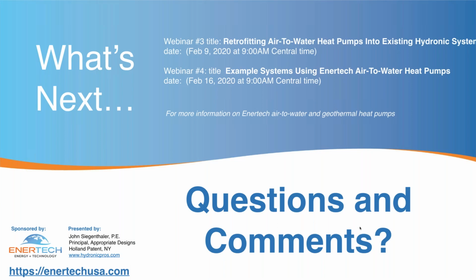I don't know, Jim, if you want to toss that one in. I guess I look at it, the energy efficiency ratio working with a chilled water temperature of 45 to 55 degrees is probably a very small amount lower than an all air system would be, but you're also picking up versatility. The trade-off there is, again, with a hydronic system, you can craft that cooling system into zoning much easier than what you can do on the forced air side.